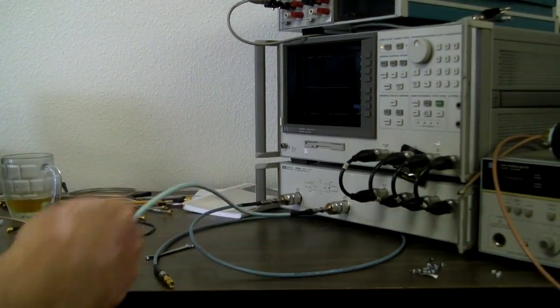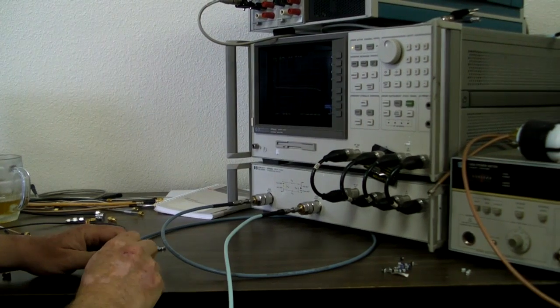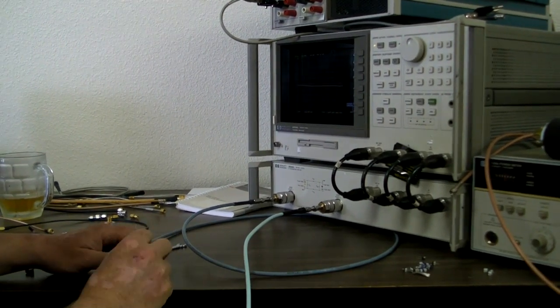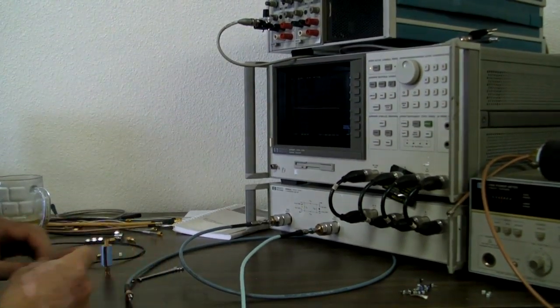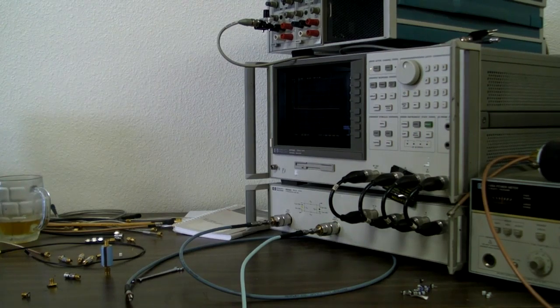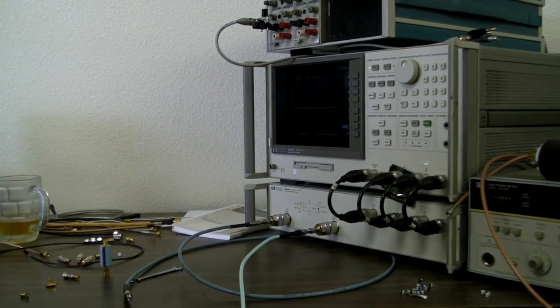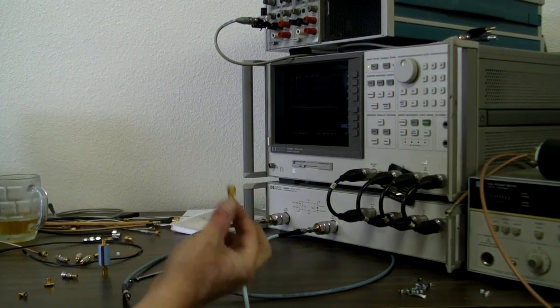I've set this up for an insertable device, male to female. Since I don't have a complete cal kit, as a matter of fact I don't even have any cal kit, I have this cobbled cal kit. We're going to assume this is zero length. At 70 megahertz, it is.